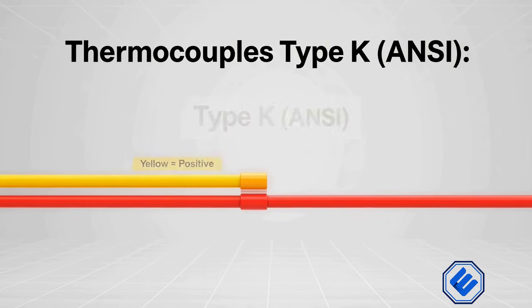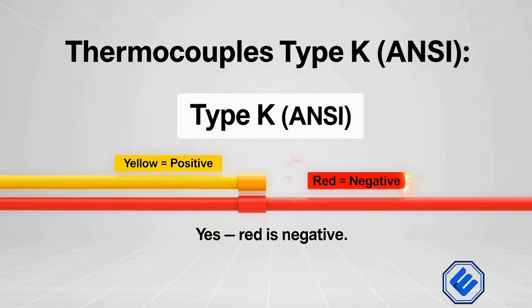Let's move to thermocouples. Thermocouples generate a tiny voltage based on temperature difference. There are 2 rules you absolutely cannot break. Using copper creates a new thermocouple junction and ruins the reading. Rule number 2, watch polarity. Thermocouple color codes can be confusing. For example, in ANSI type K, yellow is positive, red is negative. Yes, red is negative. Always check the manufacturer's chart before wiring.